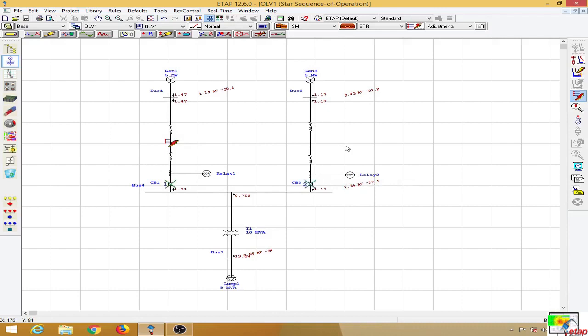Both feeders being isolated is an unwanted condition. What we can do is provide a directional overcurrent relay such that the circuit breaker operates only when the current flows from the bus to the line. In this case, the current is flowing into the bus here, and the fault current is going out of the bus there.